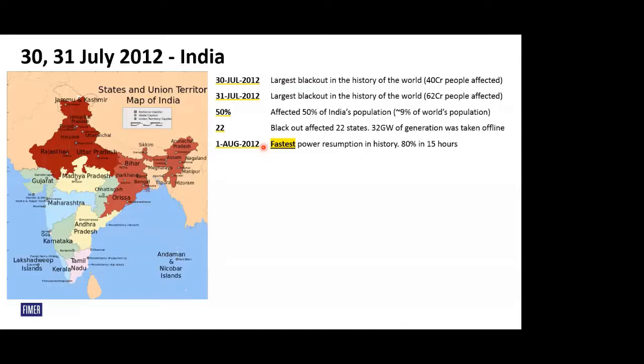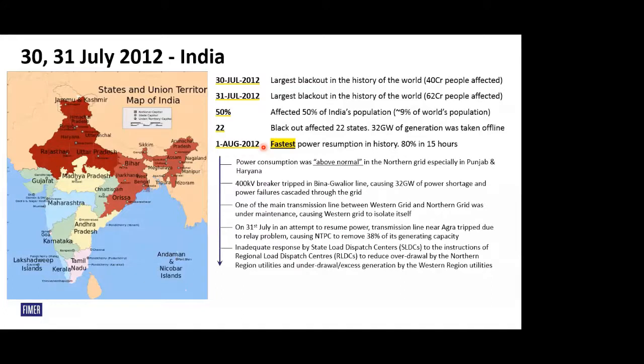The question is, why did this happen? Let's see if this gives us some thought process. It happened because the power consumption was above normal in the northern grid, especially in Punjab and Haryana. You have to understand, July being a harvesting season, these two states are predominantly into agriculture and farming. They overload the grid, and we do have examples of the 11 kV distribution grid in Punjab continuously having a voltage of 8.8 kV because of the overload, and you're not supposed to trip.